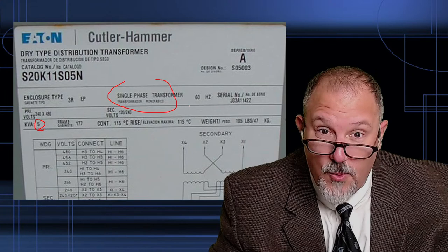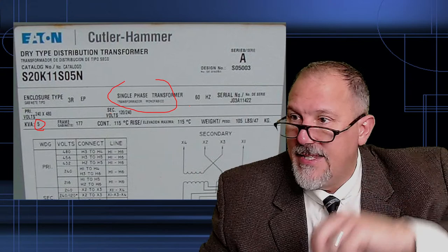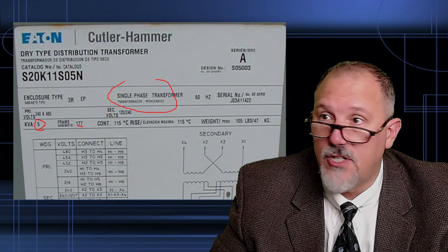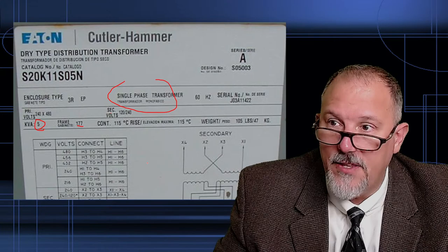Impedance of transformers, 25 kVA and larger. So I'm not required to put a percent Z on here, but let's see. Is there a percent Z? And there's a frame. I don't see a percent Z. So there's no percent impedance on this transformer. It's not required by the code. It's not necessarily required by the standards.